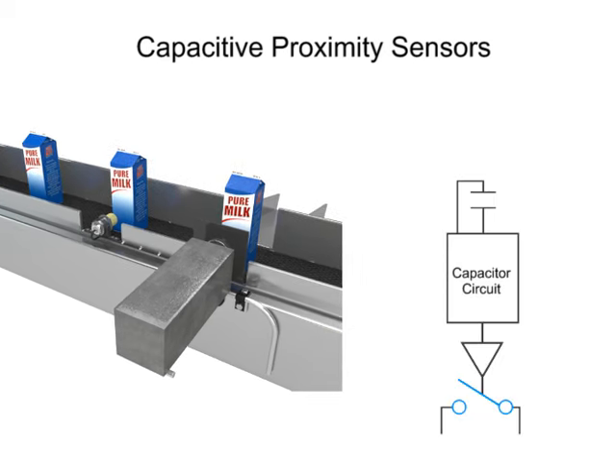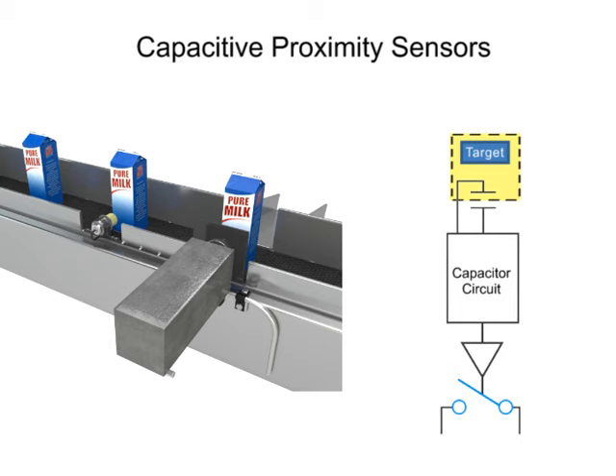Two small plates located in the front of the sensor form a capacitor. As a target enters the sensor's range, the capacitance of the two plates increases, thus causing a change in the oscillator frequency which also activates the sensor's output, either normally open or normally closed, respectively.